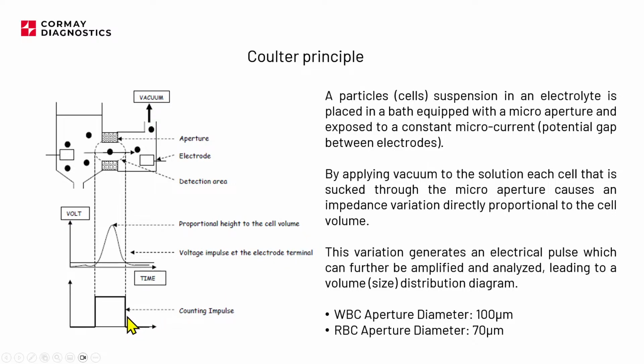Another piece of information recorded by the analyzer during this measurement is the counting impulse. When the size of the particle is higher than some specific threshold, the analyzer will consider this particle as a cell. Because, as I said, some particles like PLTs in the WBC channel are not counted. The device doesn't care about the PLTs in the WBC channel. PLTs are below the threshold for white blood cells, so they are not even counted by the analyzer at this point.